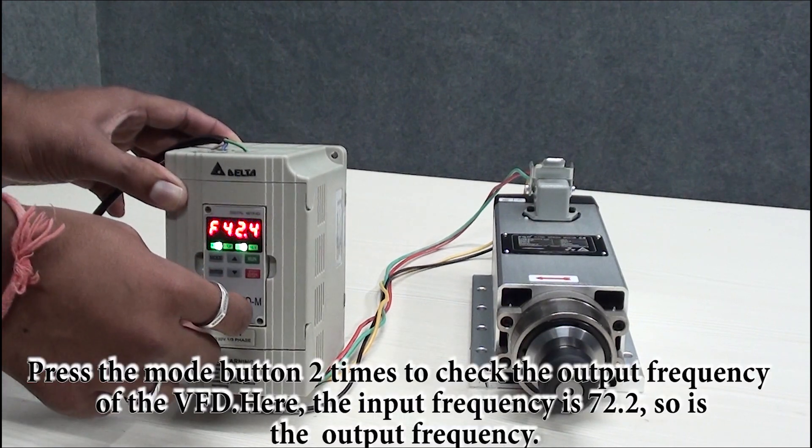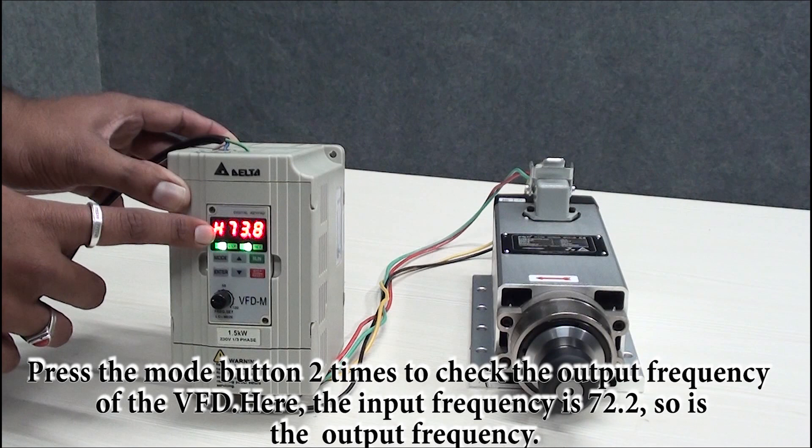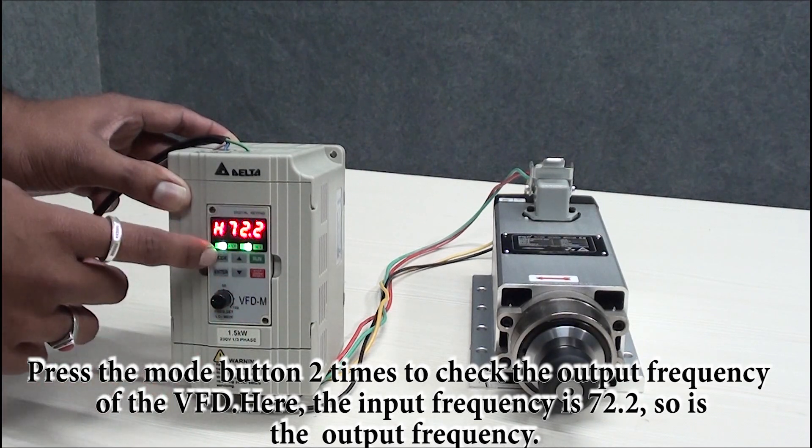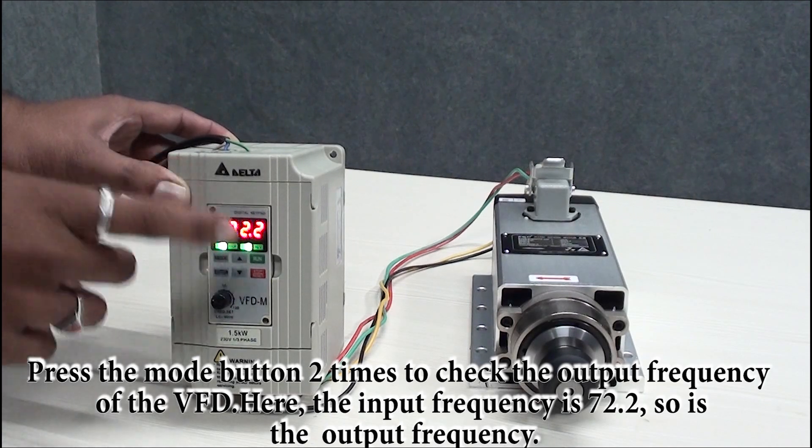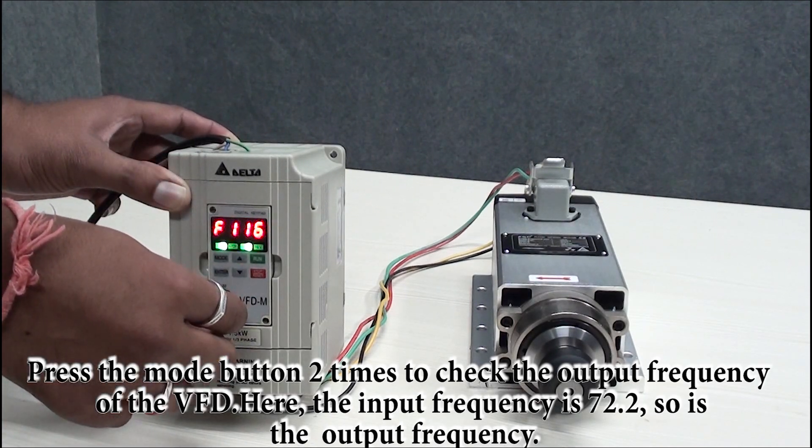2.8 ampere. As you vary the master frequency, in H you can observe output frequency at UVW. This is 72 hertz and in master frequency is also 72 hertz, means input frequency equal to output frequency. As you vary input frequency master frequency, the output frequency also varies.